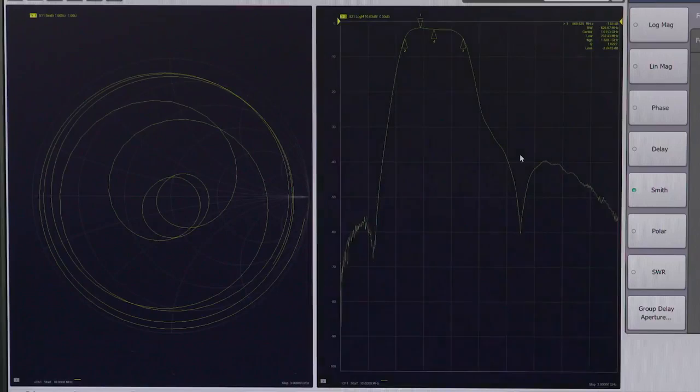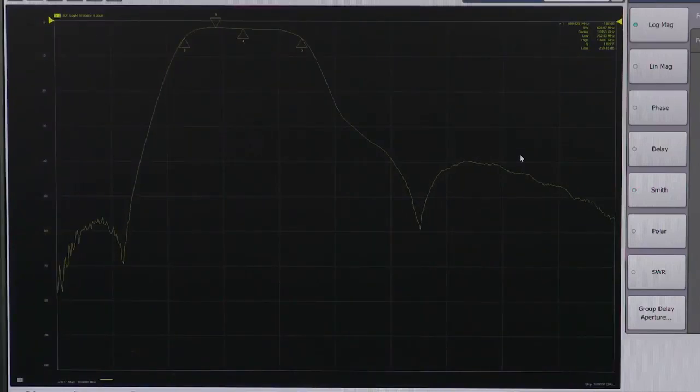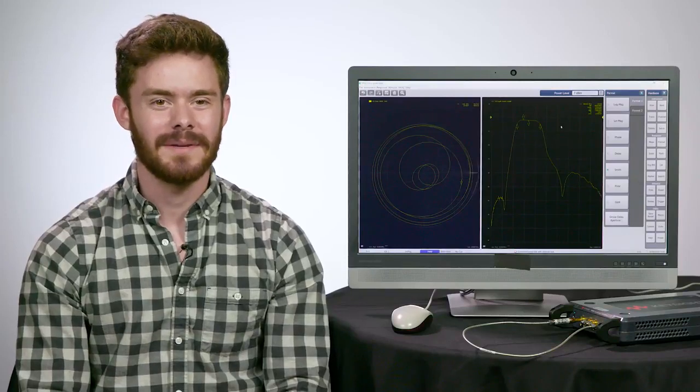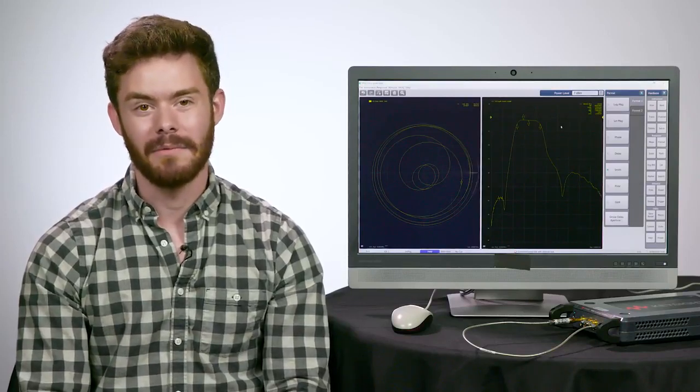Lastly, let's learn about how to speed up measurements and improve their accuracy. First, I'll double click on the S21 window to maximize that on screen. In order to speed up the measurements, we need to make the intermediate frequency bandwidth, or IF bandwidth, wider.